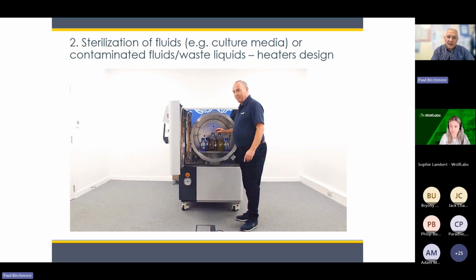The enhancement that Neil mentioned takes the heating of the water to make steam outside into a separate, what we call a steam generator. And then you have some extra features as well. That I'm going to call a dry system. So you've got the two types. You can use the wet system for, in this example, the media prep. But as Neil pointed out, you could use an enhanced version, which I'm going to call the dry version, for media prep. You could use either system for this type of load.